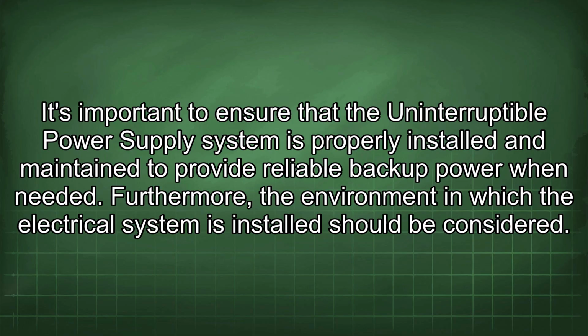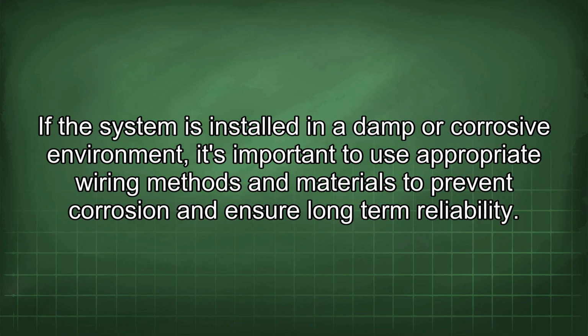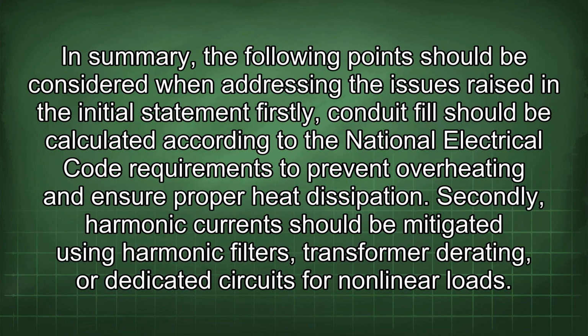Furthermore, the environment in which the electrical system is installed should be considered. If the system is installed in a damp or corrosive environment, it's important to use appropriate wiring methods and materials to prevent corrosion and ensure long-term reliability. In summary, the following points should be considered when addressing the issues raised in the initial statement. Firstly, conduit fill should be calculated according to the National Electrical Code requirements to prevent overheating and ensure proper heat dissipation.